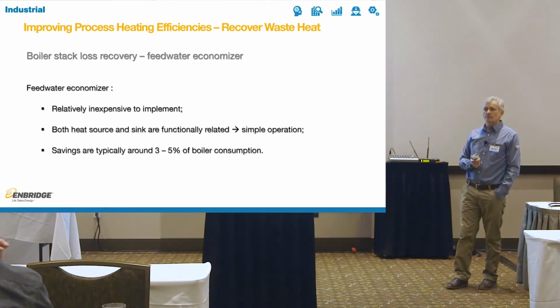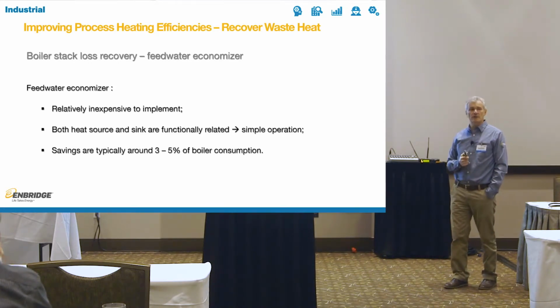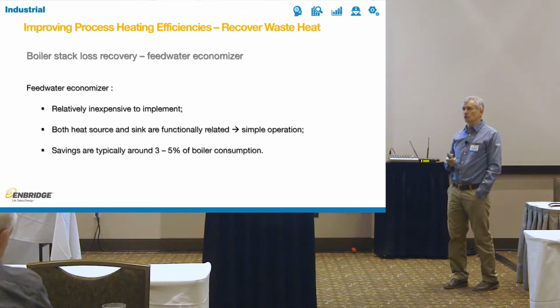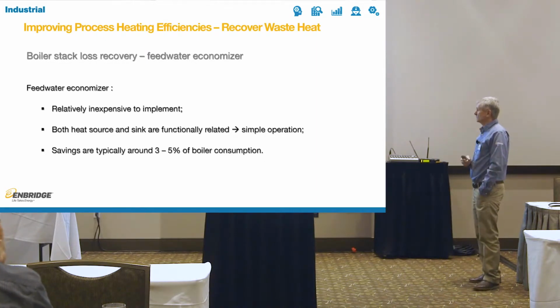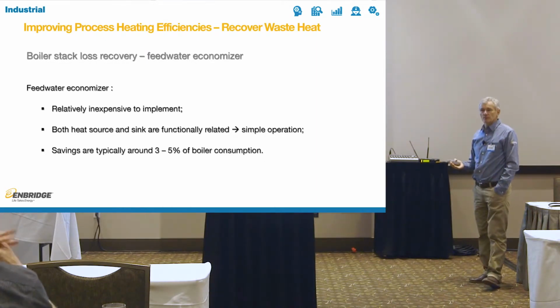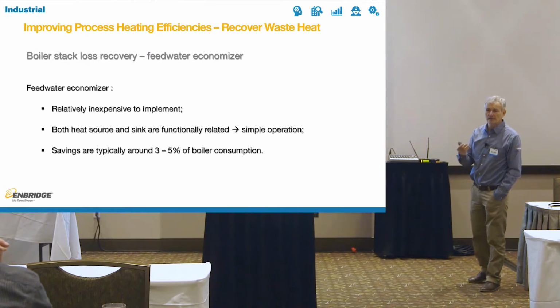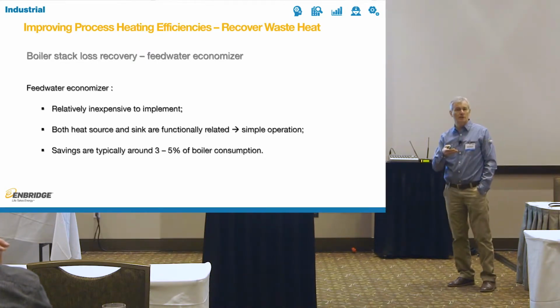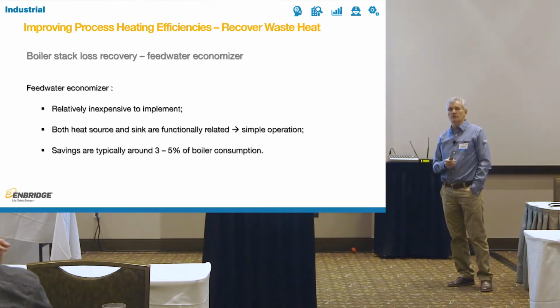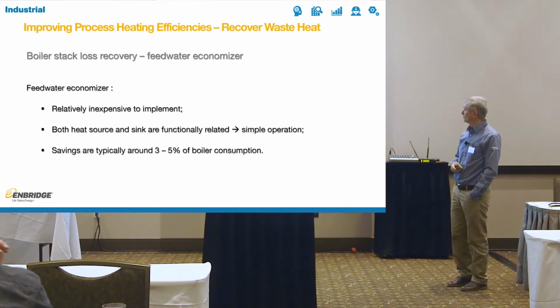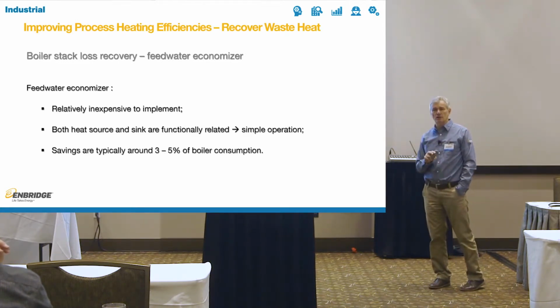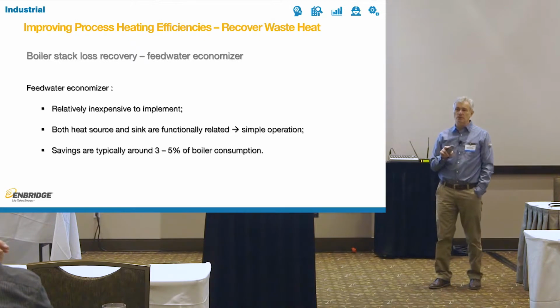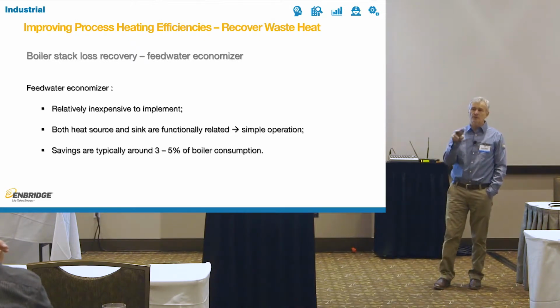Feedwater Economizer. Most of you are familiar with the term and know what it is. It's relatively inexpensive to implement. You put a coil essentially around the stack, put the boiler feed water through it, and you recover some of the heat out of it. Both heat source and sink are functionally connected, so it's simple to operate. If the boiler operates, feed water is being used, and the Feedwater Economizer is being used to recover the heat.